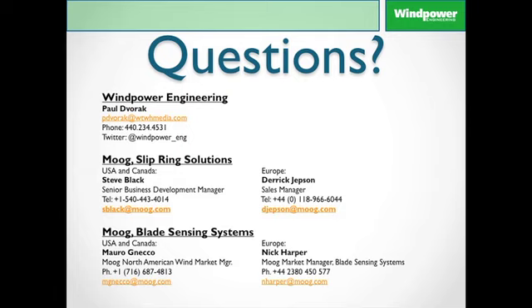Yes, Paul, that's a very good question. The good thing about the detection system is that the calibration is automatic. Once the engineers have commissioned the system in the wind turbine and installed the sensors and connected it up and got everything communicating, the system will self-calibrate over a period of time. What it is essentially doing is, as the turbine is operational, it's measuring the mass of the blade, and it uses that number to look for changes. As the ice accretes on the blade, that mass obviously increases. So the calibration is inherent in that very process.